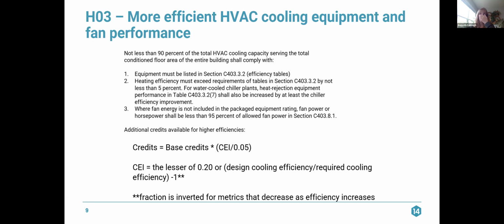And I'm sorry, it should say cooling efficiency there. The cooling efficiency must exceed the requirements by not less than 5%. So again, that same 5% that we were looking for with the heating efficiency. For water-cooled chiller plants, the heat rejection equipment performance in table C403.3.27 shall also be increased by at least the chiller efficiency improvement. So you want to see that same minimum 5% effectiveness improvement for your heat rejection equipment.